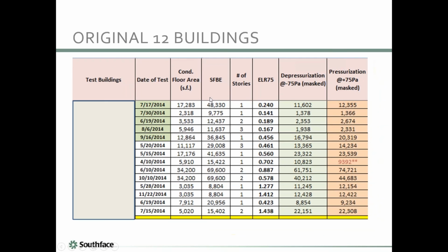We also, as part of the Advanced Commercial Building Initiative effort in the last couple of years, at the beginning chose a dozen buildings, and we decided to really study them in great effort and do energy monitoring. And of those 12 buildings, there were different types of occupancy. Of those 12 buildings, 5 were part of our Earthcraft Light Commercial program. Some were offices, some were retail, some were food, I forget all the different ones. But we blower door tested those. So the question was, how do those 5 compare with the randomly chosen 7 others, which had similar types of occupancy? And that's one way of looking at the data.